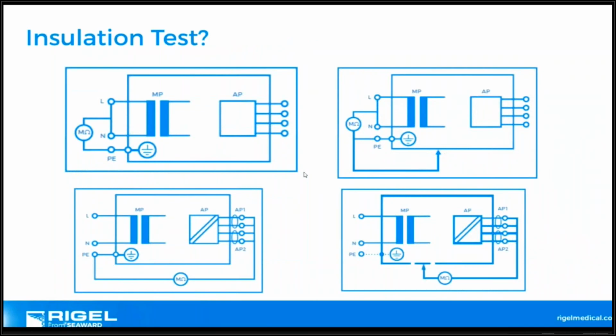Insulation tests, not mandatory. No insulation test is mandatory, even with 60601. But this is a DC test, so we have various voltages, typically 500 volts. So 500 volts would be applied. It's a bit like a DC dielectric strength test. So between the applied part, between the connectors here, we short that. We measure the resistance in megaohms by applying 500 volts DC between the protective earth and the live or hot and neutral conductors.